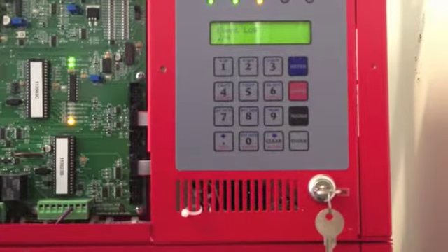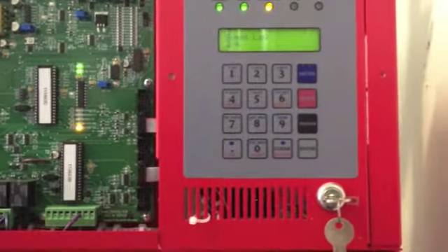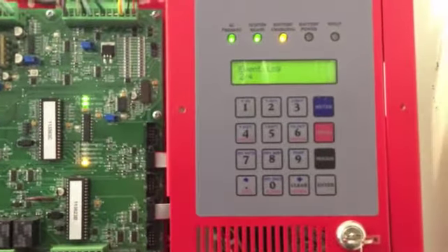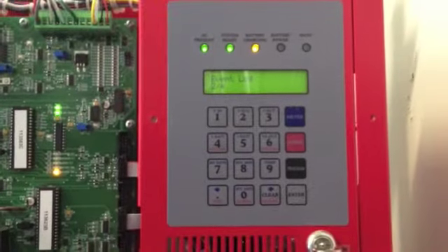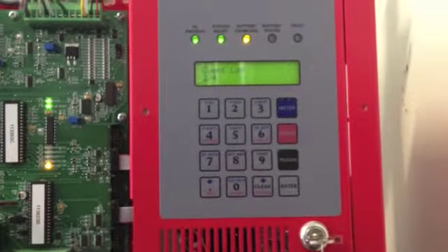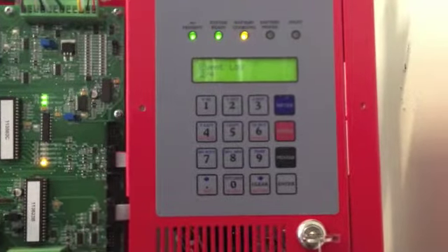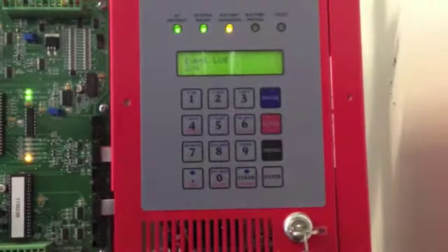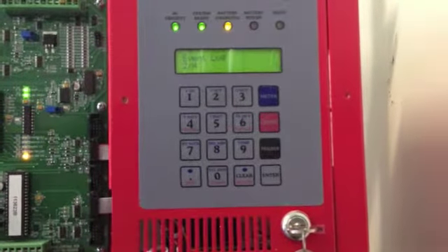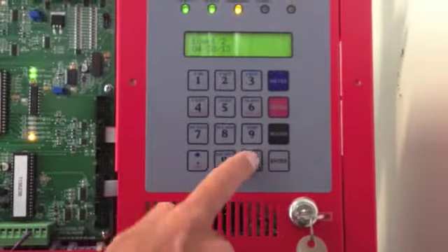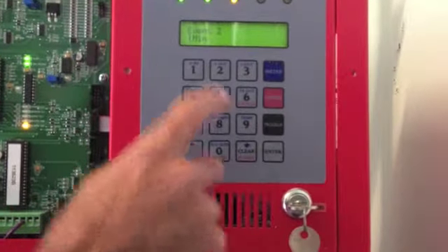1 or 2 times a day, that's acceptable. Once or twice every other day, even better. Once or twice a month, better yet. Right. If it's once or twice a month or every other day, but it's for 45 minutes, that's a problem. You know, we don't want to over-exercise the batteries for no reason. So that's what we're looking for when we look in this log. And if we select one of these guys, you know, this is 2 of 4. Again, we get the date, the time, the duration.